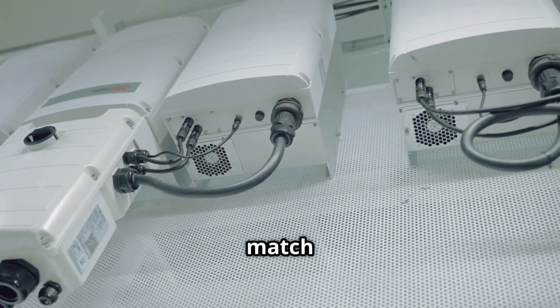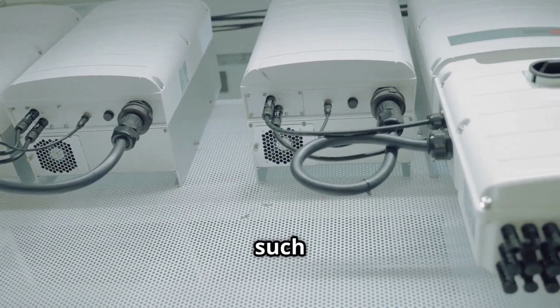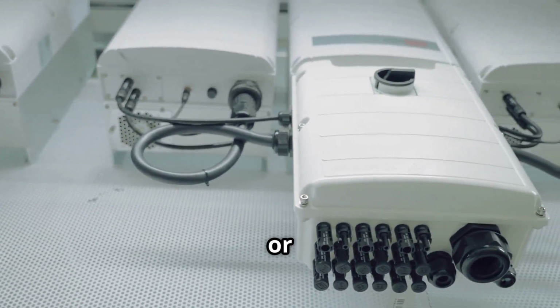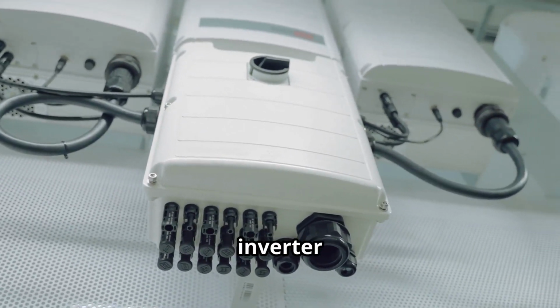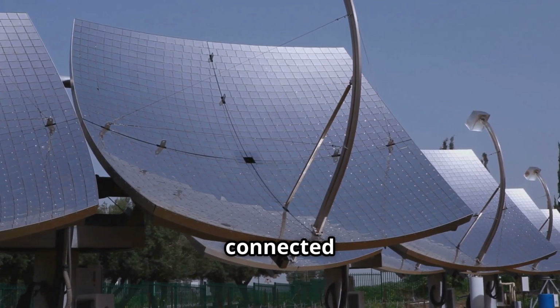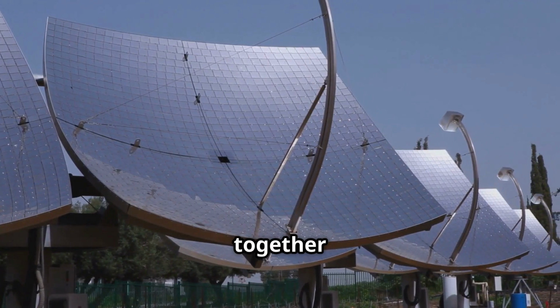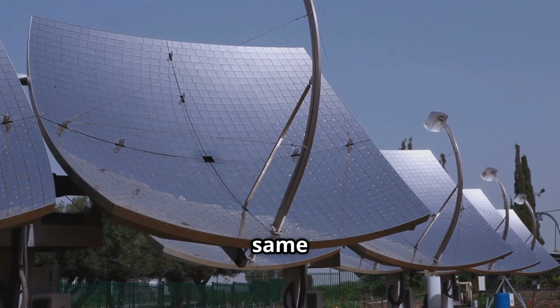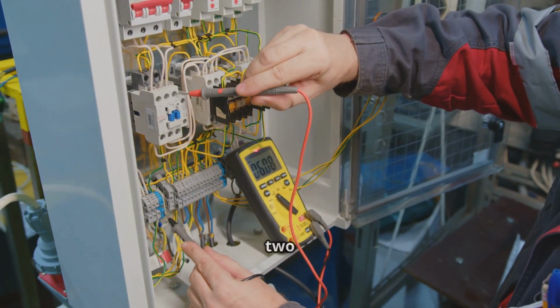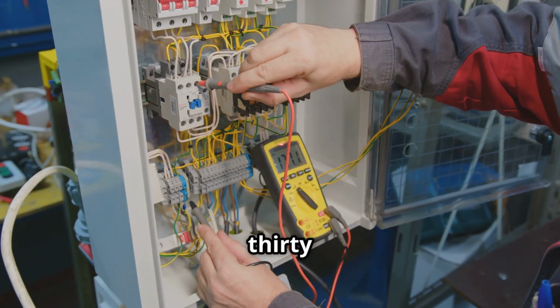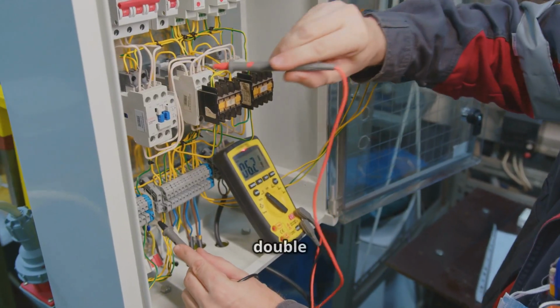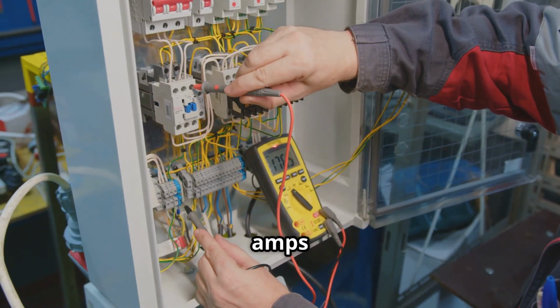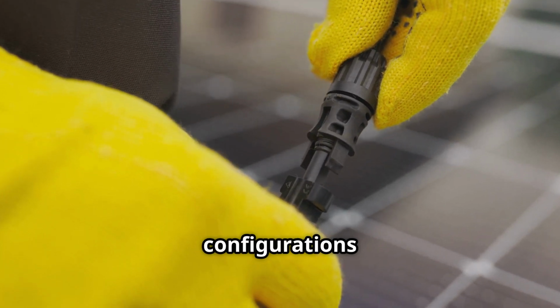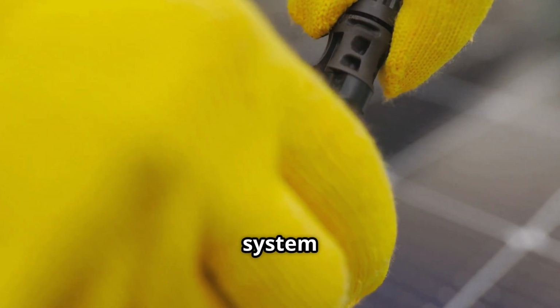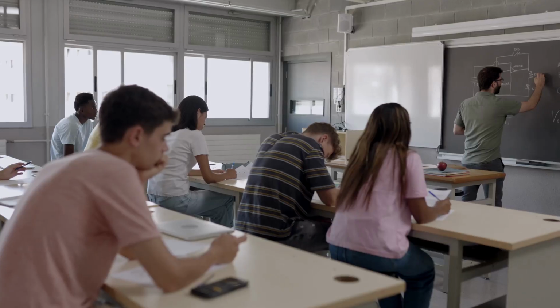This is useful when you need to match a higher voltage requirement, such as charging certain battery banks or running an inverter. On the other hand, when panels are connected in parallel, the currents add together while the voltage stays the same. So, if you connect two panels in parallel, you'll still have 30 volts, but the current will double to about 16.66 amps. Understanding these configurations is key to designing a system that meets your voltage and current needs without overloading any component.